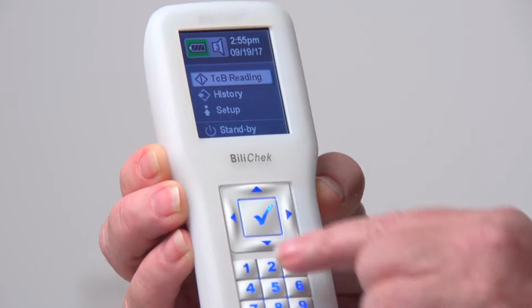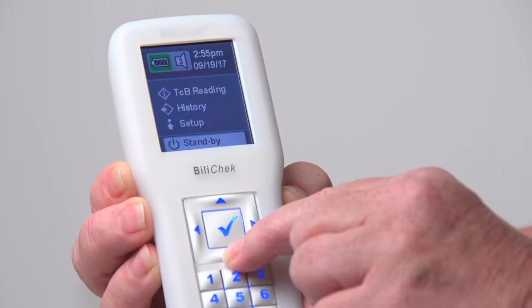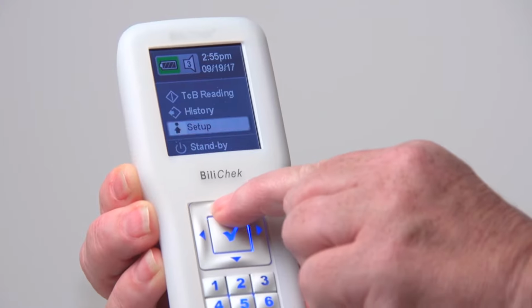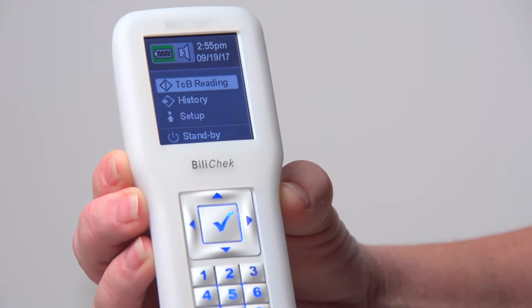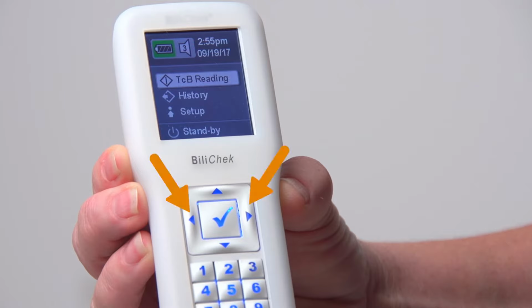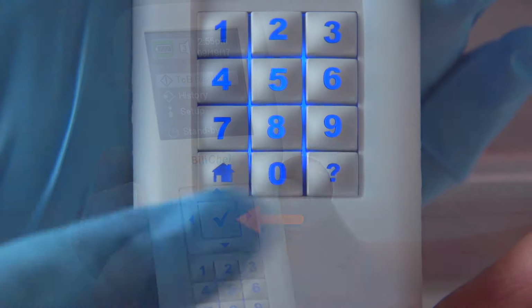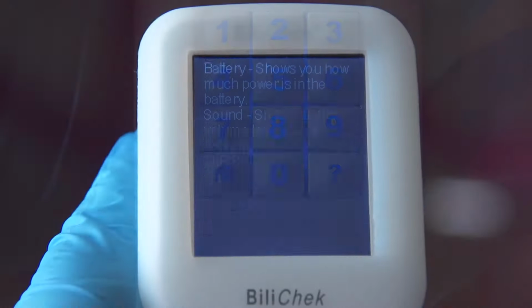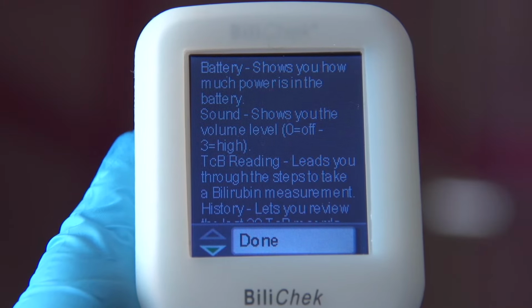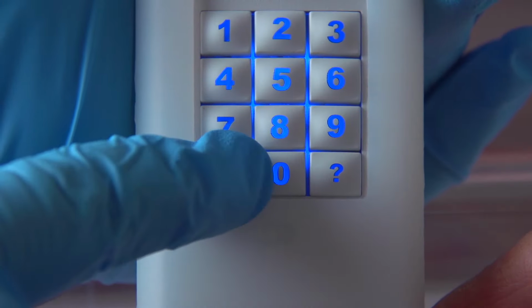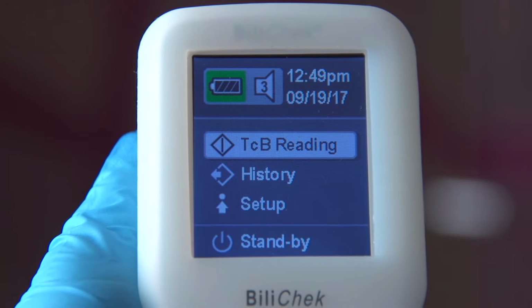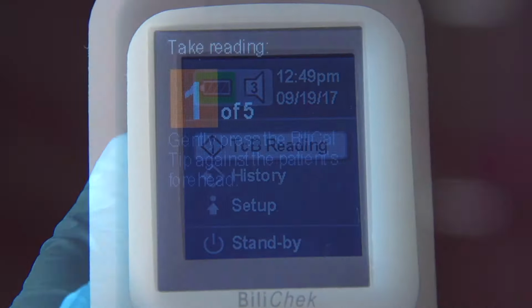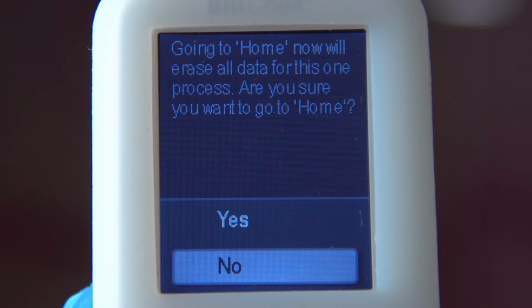Operation of the Bilichek involves the use of the keypad to navigate through the on-screen menus. Use the up and down arrow keys to scroll through the menu options and settings. Use the left and right arrow keys to perform the actions specified on the screen. Use the Enter key to save the setting. Press the Help key at any time to display instructions for that action. Press the Home key to return to the home screen at any time. If you return to the home screen in the middle of a reading, you must restart the measurement process.